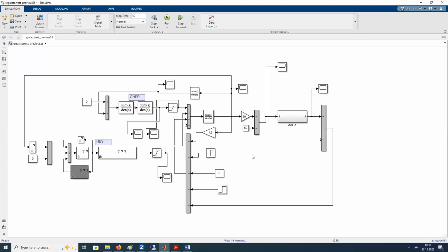But due to all these troubles with the lower frequency, we lost some generation as well. Here we have an additional, different generation loss. So we have a first, initial deficit due to any fault, and here we got the secondary generation loss due to the low frequency. And here we could see how our automation could deal with this problem.